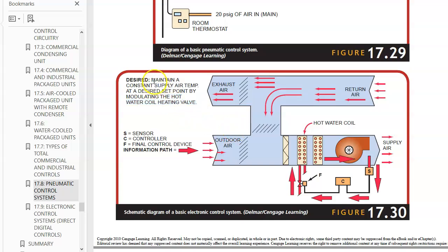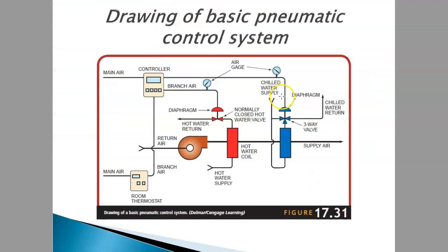So actually this above figure 17.30 is desired to maintain constant air temperature at the desired set point by modulating the hot water coil heating valve. So what happened? This is the controller, the thermostat is a controller. It has a sensor over here, goes right to the controller, and this controller controls the valve of what? Of hot incoming water.